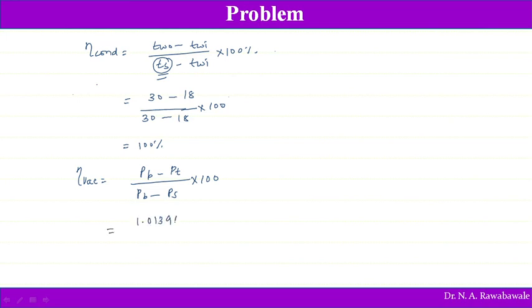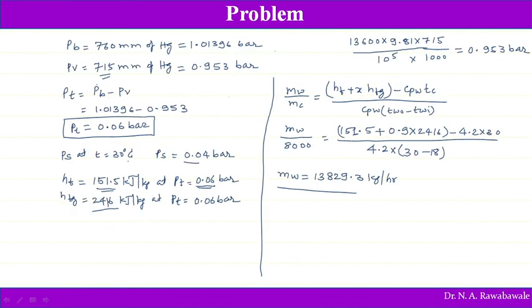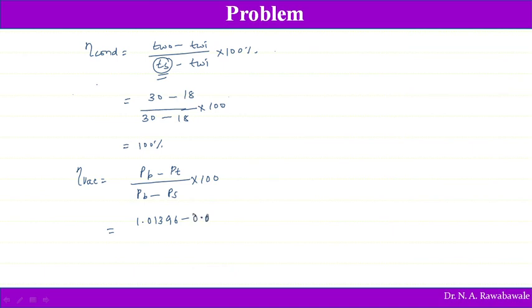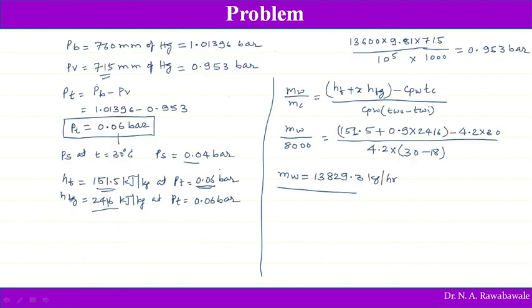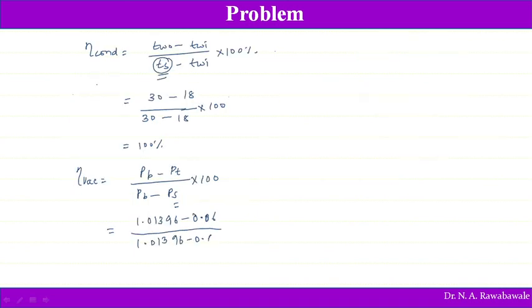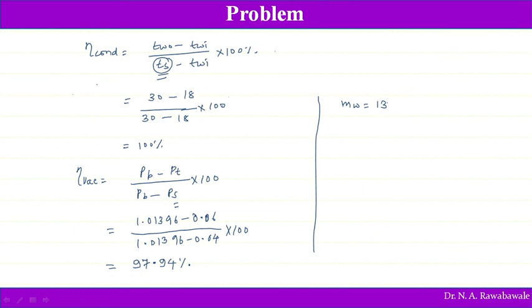Vacuum efficiency: PB = 1.01396, PT = 0.06, PS = 0.04 bar. Vacuum efficiency = (1.01396 − 0.06) / (1.01396 − 0.04) × 100 ≈ 97.94 percent. Summary of Problem 3 results: mass flow rate of cooling water MW = 13,829.3 kg/hr, condenser efficiency = 100 percent, and vacuum efficiency ≈ 97.94 percent.